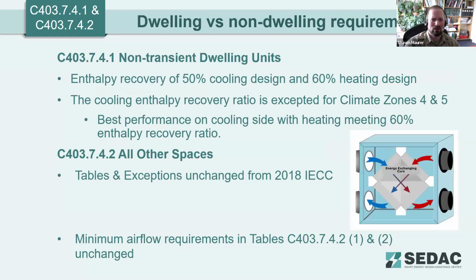Dwelling versus non-dwelling unit requirements for energy recovery. Non-transient dwelling units have enthalpy recovery of 50% of cooling design and 60% of heating design. The cooling enthalpy recovery ratio is exempted for climate zones 4 and 5, so only the heating side enthalpy ratio is considered, and then the cooling side is whatever you can achieve when the heating side meets that 60% target. For all other spaces, the tables and exceptions are unchanged as far as the minimum airflow that triggers when you have to have energy recovery.